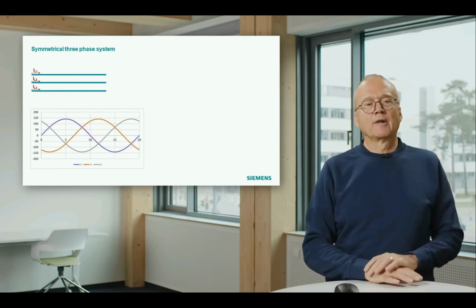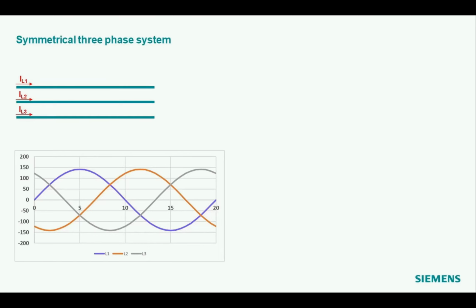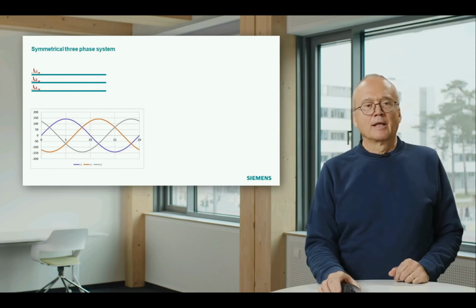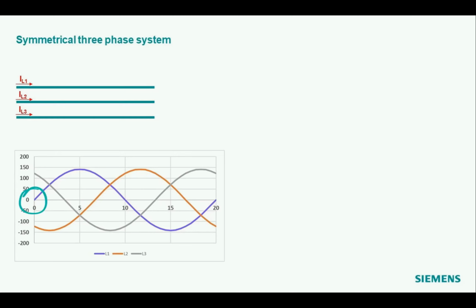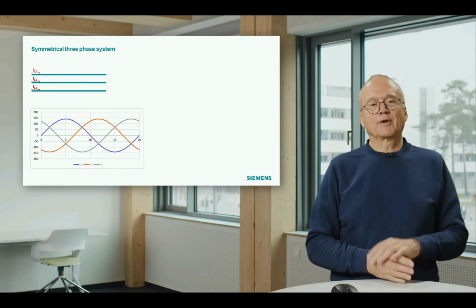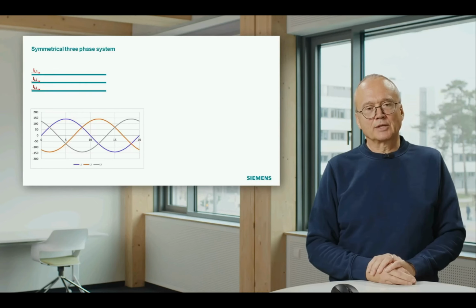We do that because we have sine waves in a symmetrical system. That means the current IL1 has, for instance, this purple sine wave. The current in phase 2 has the orange sine wave. And in phase 3, we have the gray sine wave. We see here the range in this diagram is 20 milliseconds. That is exactly one period in a 50 Hertz system. The purple sine wave starts at zero with a zero crossing. The orange sine wave has its zero crossing nearly 7 milliseconds later. That is a phase shift of 120 degrees. And the gray curve has its zero crossing another 120 degrees later. That means these three currents in a symmetrical three-phase system have a phase shift of 120 degrees between them.